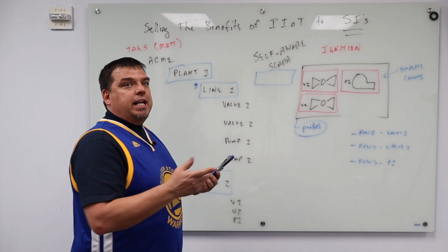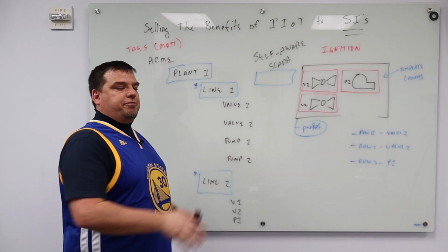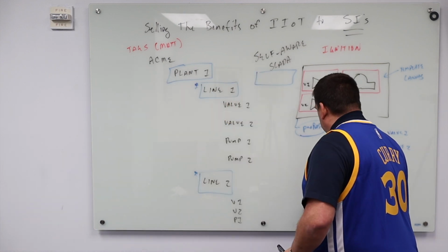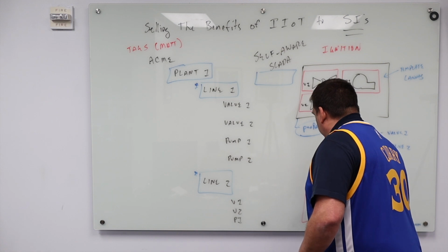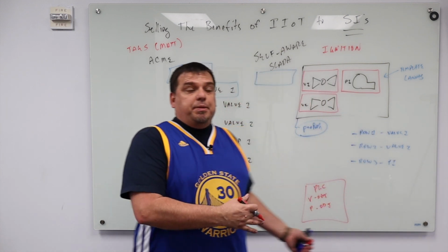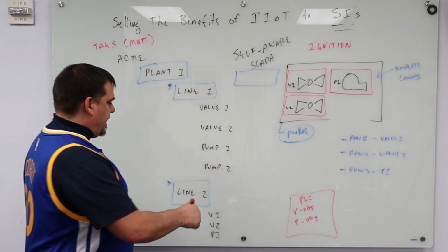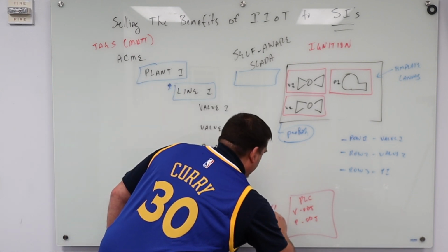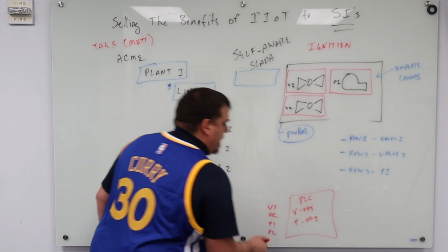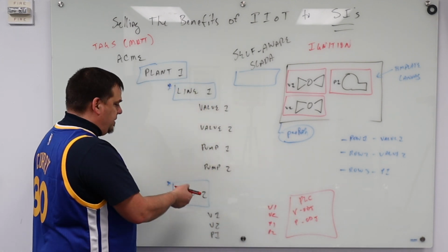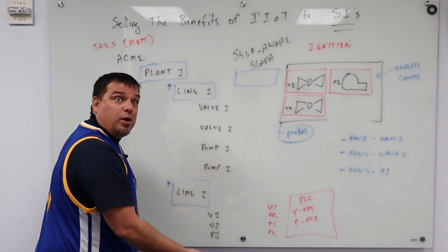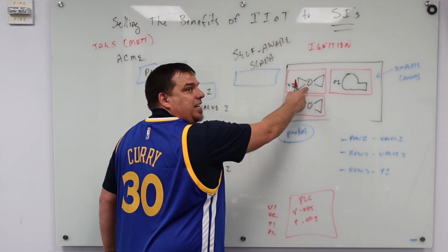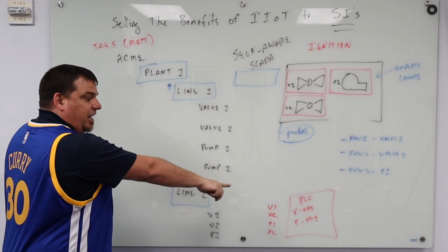Yeah, what we can do is, so here's basically what happens. Okay, so for the self-aware SCADA, here's what happens. In my PLC, I build a valve object, and I build a pump object. Then inside my PLC, I create instances of that object. In this case, I've created 2 instances of the valve and 2 instances of the pump. So when I have a V1 and a V2 and a P1 and a P2, as soon as I plug the PLC in and publish over MQTT, then it's V1, V2, P1, P2. Then when we go to our window, which is also built, we have this V1 template, which is a template that I developed for that object.